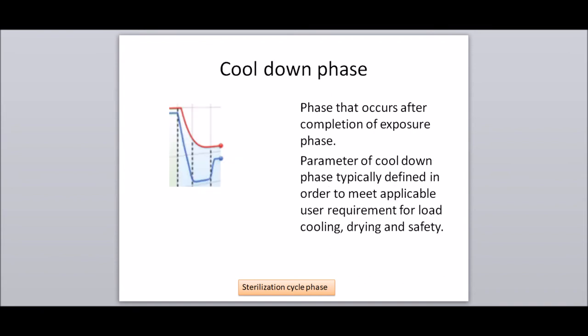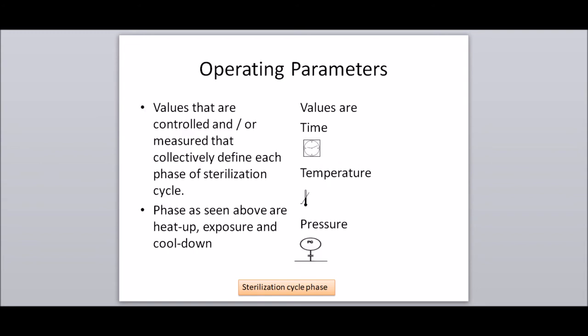Cooldown phase: the phase that occurs after completion of the exposure phase. The parameters of the cooldown phase are typically defined to meet applicable user requirements for load cooling, drying, and safety. Operating parameters: values that are controlled and/or measured that collectively define each phase of the sterilization cycle — heat up, exposure, and cool down.